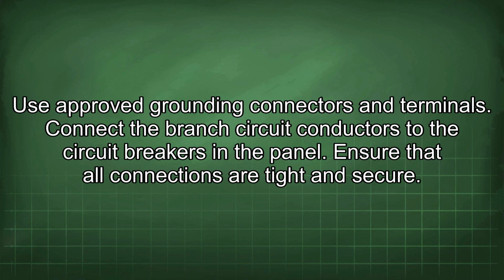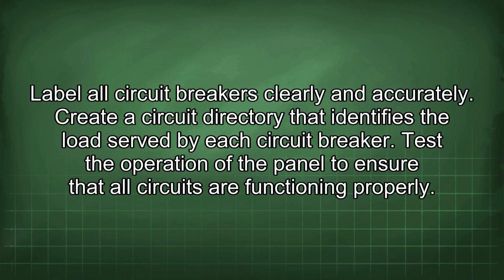Connect the branch circuit conductors to the circuit breakers in the panel. Ensure that all connections are tight and secure. Label all circuit breakers clearly and accurately. Create a circuit directory that identifies the load served by each circuit breaker. Test the operation of the panel to ensure that all circuits are functioning properly.